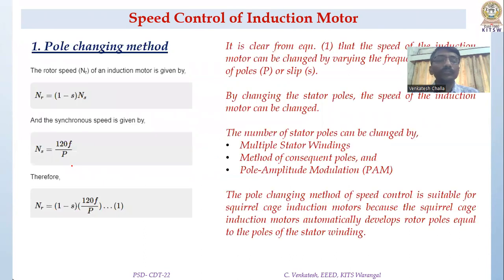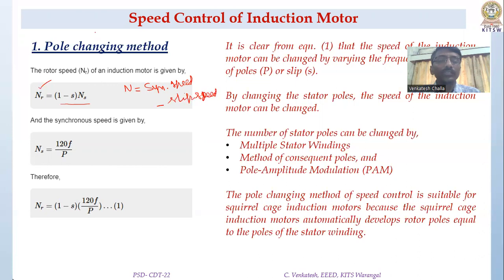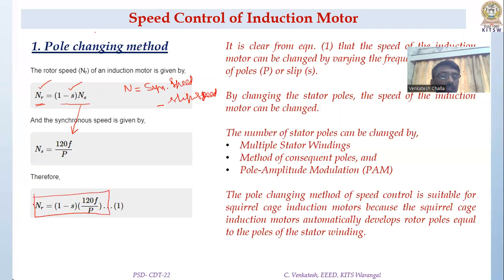The first method is the pole changing method. The rotor speed n equals (1 − s) × ns, where synchronous speed ns is given by 120f/P. So the total speed equation shows that rotor speed depends on number of poles. If the number of poles is increased, the speed will decrease. So if we can design the motor where a change of poles is possible, we can achieve different speeds.